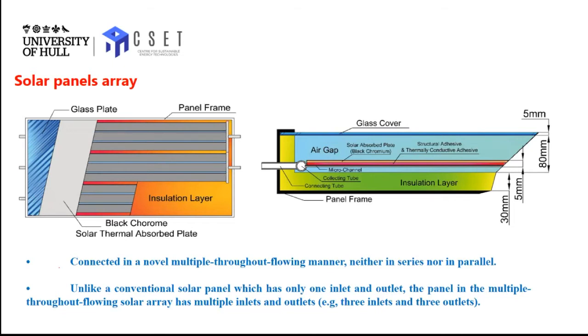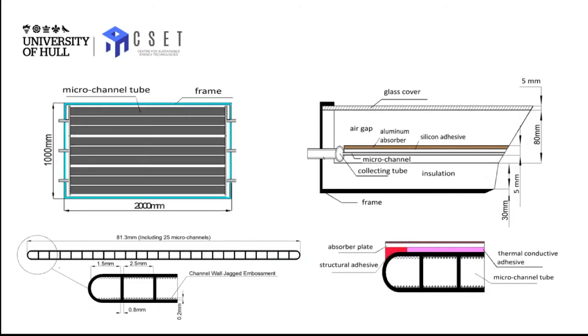Our experiment indicates that if we have 9 or 10 such panels connected in the multiple flow way, we would be able to achieve a 20 to 30% increase in overall solar efficiency. So for each panel, we make use of a microchannel structure. We have a corrugated geometry inside, which has a relatively small cross-section and leads to increased fluid flow speed and increased heat transfer between the channel wall and the fluid inside. So this leads to higher solar efficiency for the individual panel.